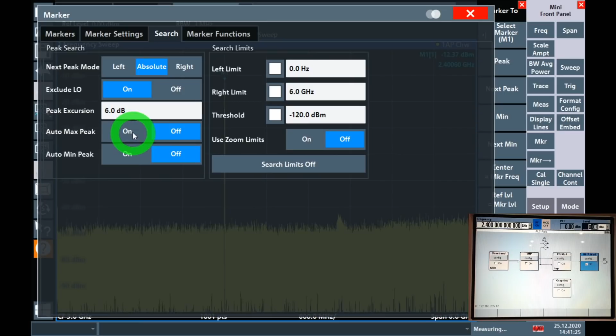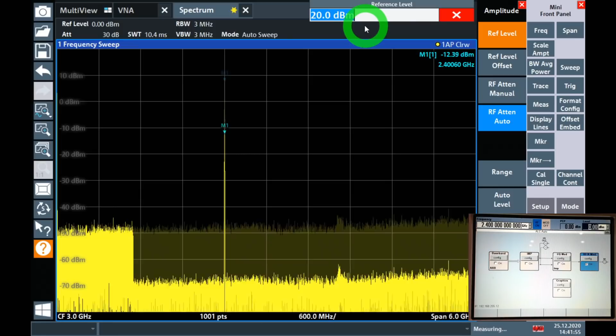Let's go ahead and increase the amplitude here. What am I looking for? Where's our amplitude? There it is. So instead of 0 dBm, let's go to 20 dBm. You want to make sure that the instrument is protected. So there you go. Of course, the amplitude hasn't changed. It's just that we now have an attenuator kick in. You can see if I go under the RF attenuator, we have a 30 dB attenuation, which is automatically selected by the instrument. So if I click on that, it will make sure that the appropriate attenuation is selected.